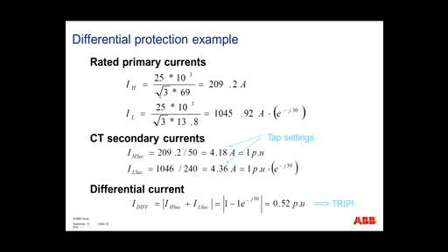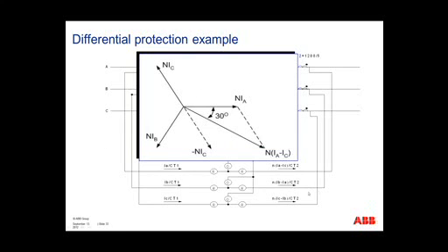We look at the numbers from our example. We calculate our primary currents: our MVA divided by our voltage level times the square root of 3, on both the high and low side. We look at our CT secondary currents: we take our primary currents divided by our CT ratio. We get our tap settings. Then when we add our differential current together, since we did not account for this square root of 3 phase shift on the low side, we can see 52%, or 0.52 per unit, excess current in our differential current, which will result in a trip. And this is just shown vectorially, the phase shift from the high and low side.